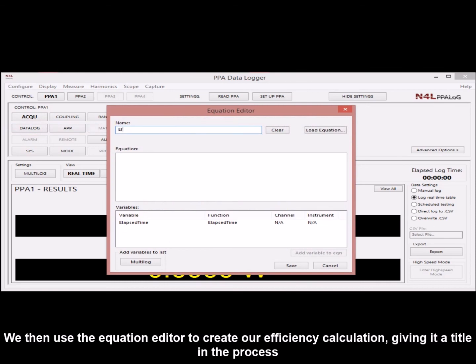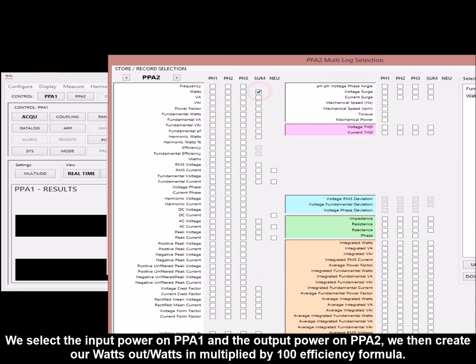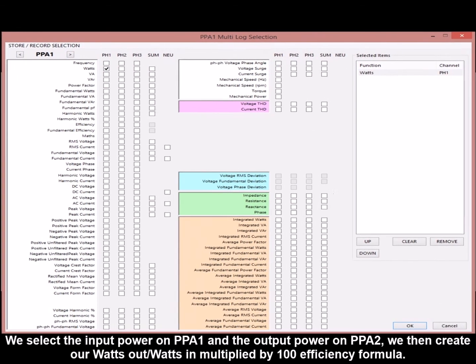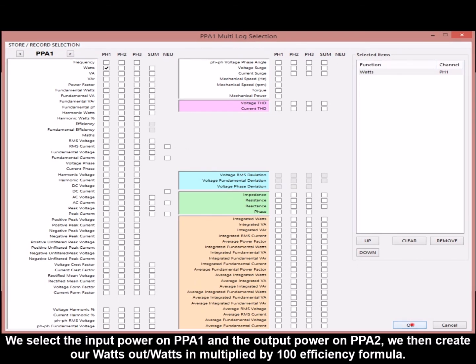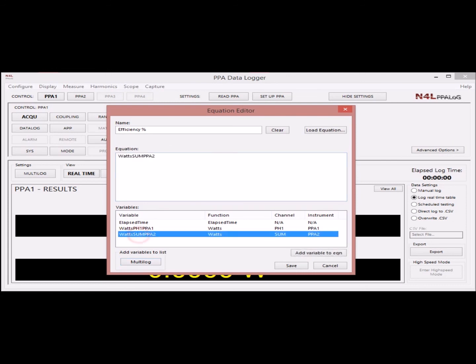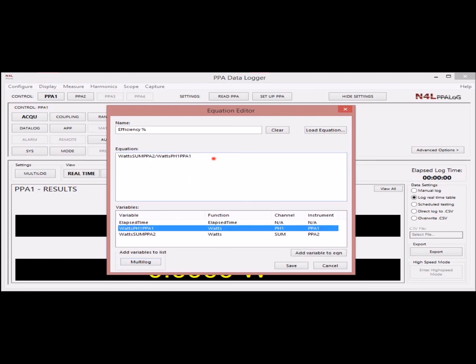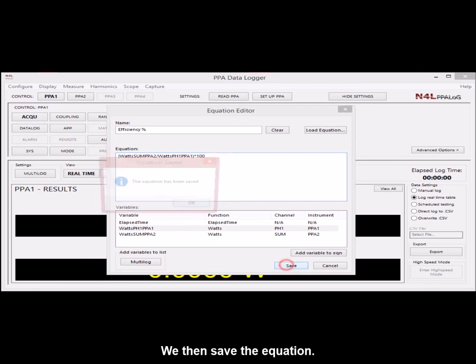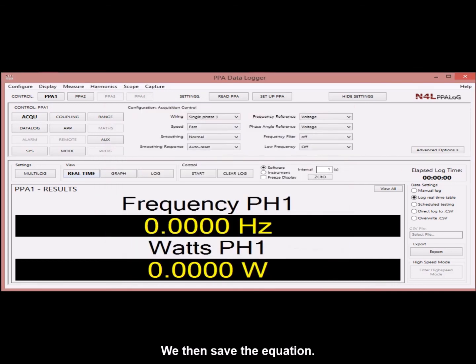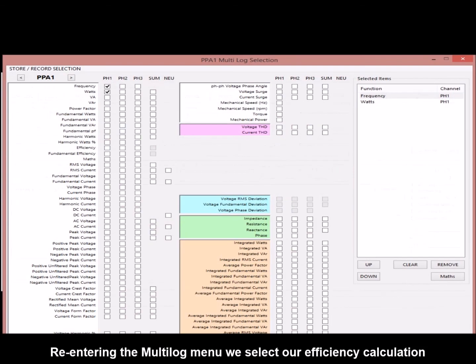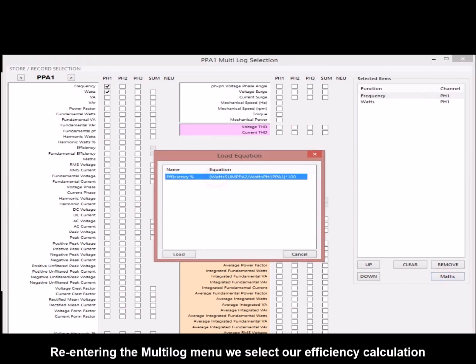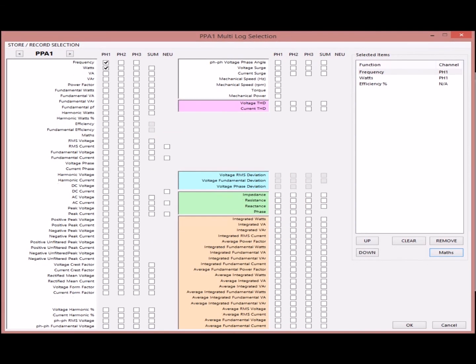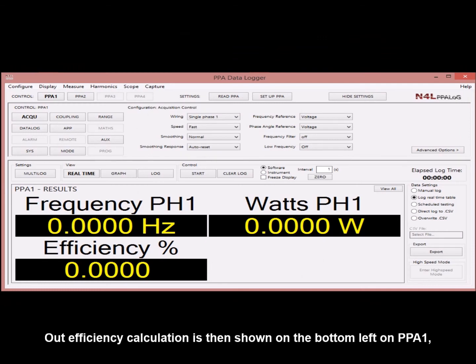We then use the equation editor to create our efficiency calculation, giving it a title in the process. We select the input power on PPA1 and the output power on PPA2. We then create our watts out over watts in multiplied by 100 efficiency formula. We then save the equation. Re-entering the multi-log menu, we select our efficiency calculation. Our efficiency calculation is then shown on the bottom left on PPA1.